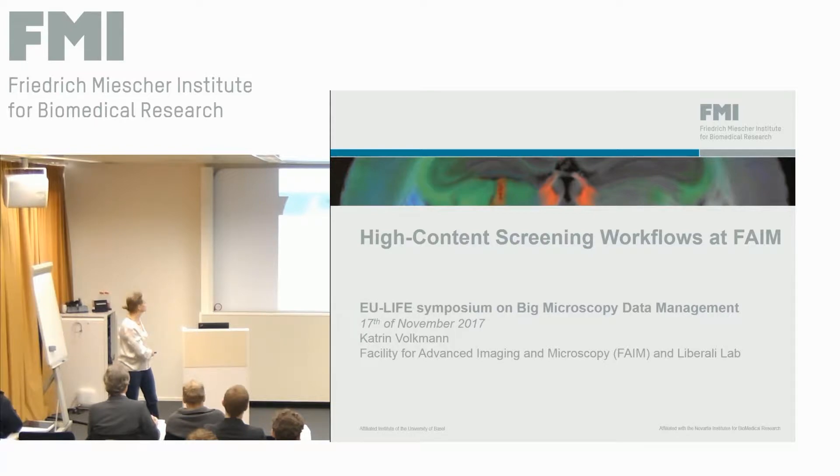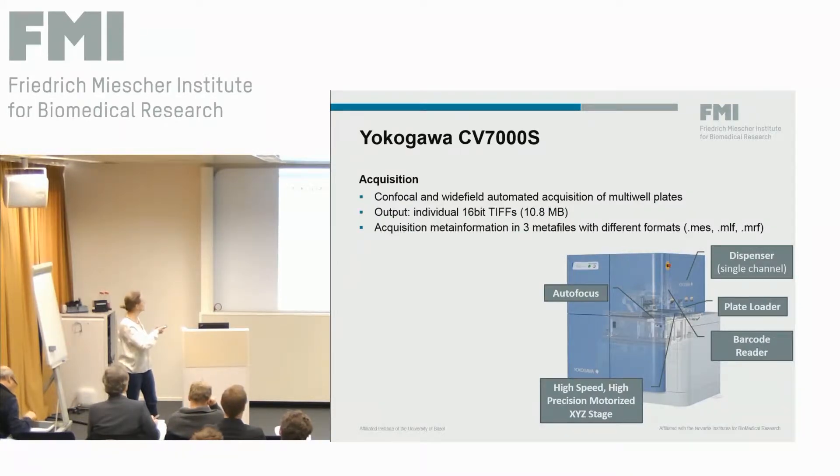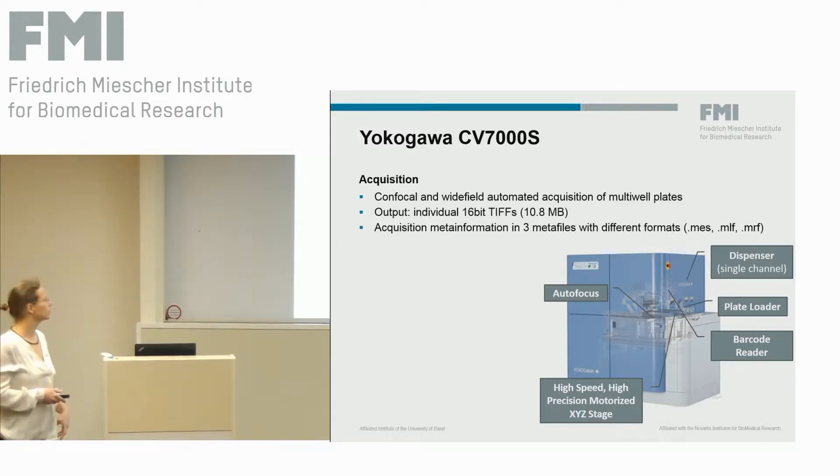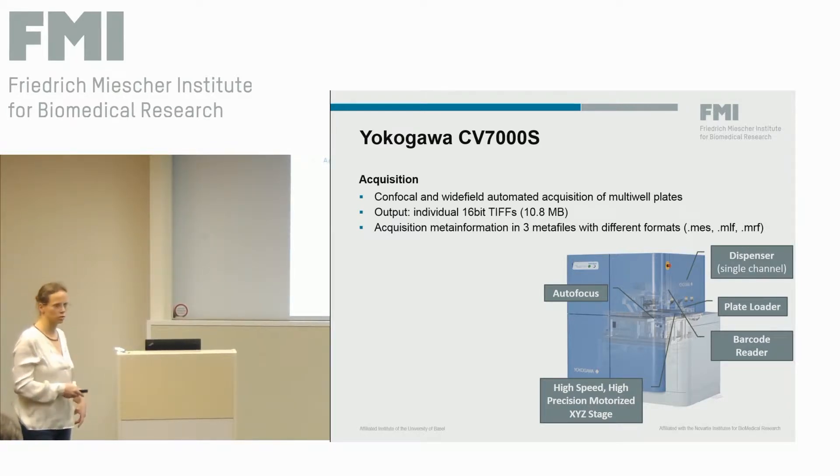Thanks for the opportunity to present. You have seen this big blue box before in the presentations of Lean and Rico — this is our high content screening microscope, the CV-7000S from Yokogawa. It features a fully automated stage, autofocus, a liquid handling module for single channel dispensing, a barcode reader, and it's integrated with a plate loading robot so loading of the plates can be done automatically. The acquisition modes can be both confocal and wide field — it's a confocal spinning disk.